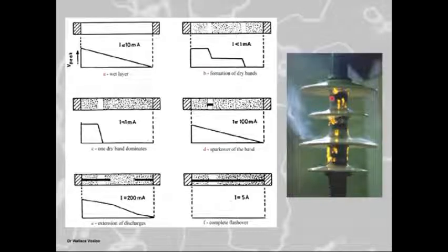But anyhow, now when we start looking at this dry band discharges, when it goes into sparking, you will hear that acoustically it will start to go more into a crackle. That type of level, you're looking at milliamps to tens of milliamps, okay? And then it will go over to hundreds of milliamps where the acoustic level will go down lower, and it starts to be a little bit more stable. And that is normally in the hundreds of milliamps. And then you reach a point where it basically goes into a full arc, and now you're going into amps.